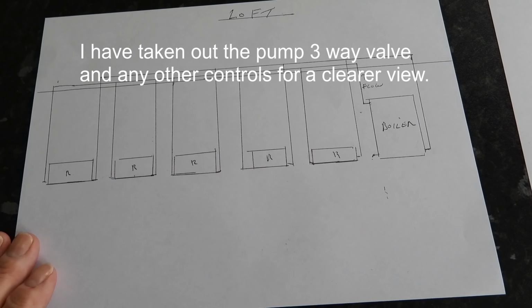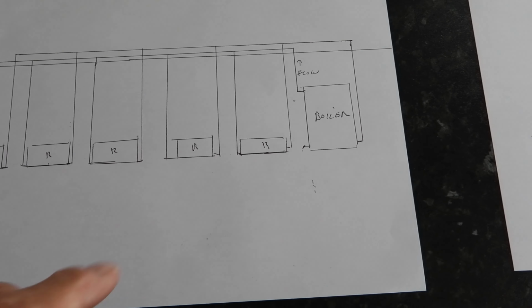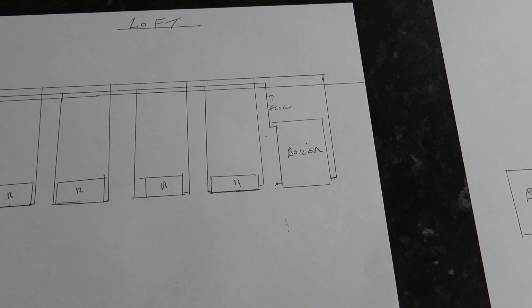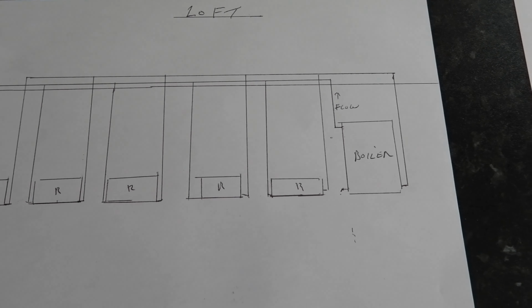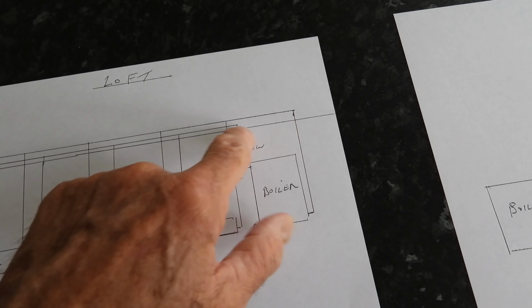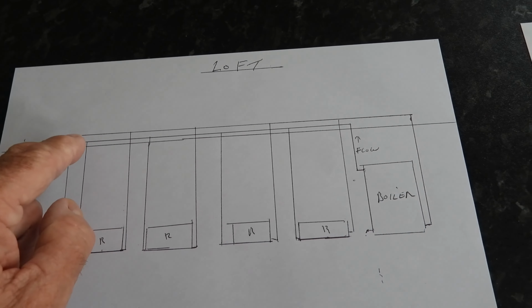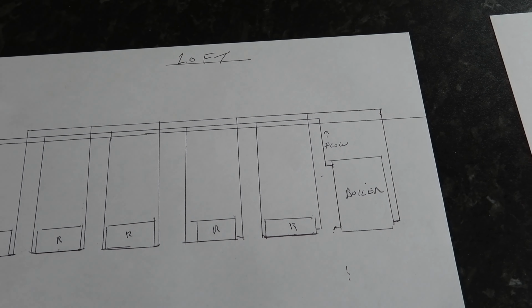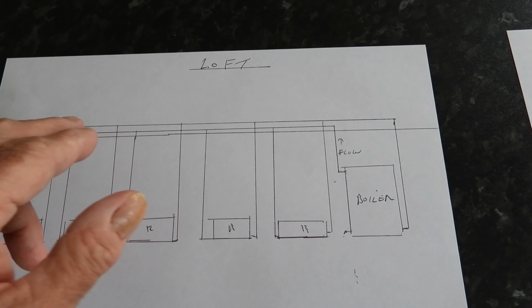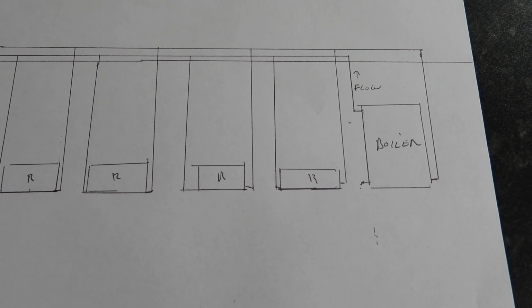Now, dealing with central heating and looking at the problems that you can get there, this is a typical example of, say, a bungalow, and it looks a bit of a funny drawing, but these are the radiators and this is the boiler, and quite often the flow and return will be taken up into the loft and all the pipes are dropped down the walls inside the bungalow, or it could indeed be your house upstairs. The pipes could be going up into the loft and dropping down into the bedrooms, but they drop down, and obviously if you ever have to drain it, or if air does accumulate, it can accumulate above these drops, and this is a typical place where you would fit one of these air release valves. Now these automatic air valves are very cheap. They're about £6 to £8 each, and you could fit them on the top of each of these drops, so that whenever you drain the rads out to do any work or anything, at least it wouldn't airlock up and it would keep the air automatically clear.